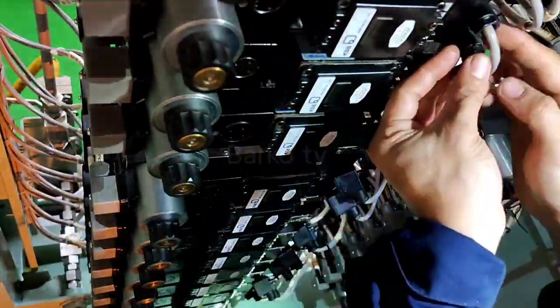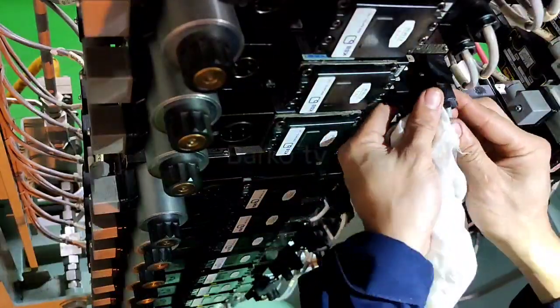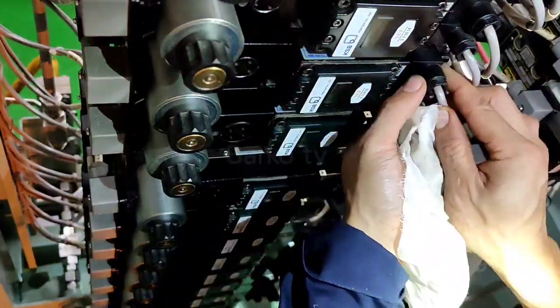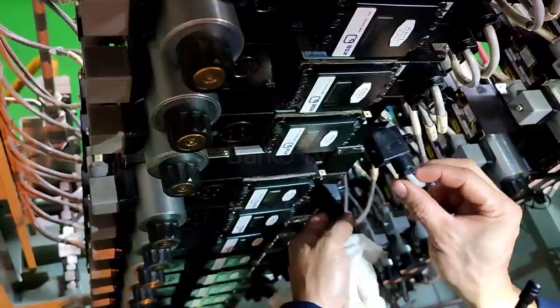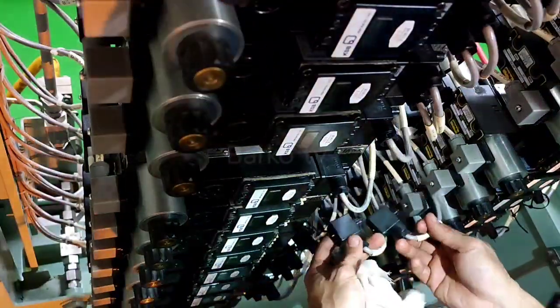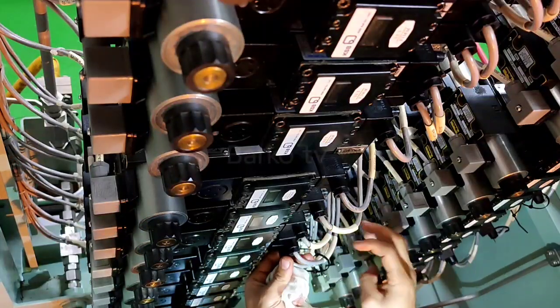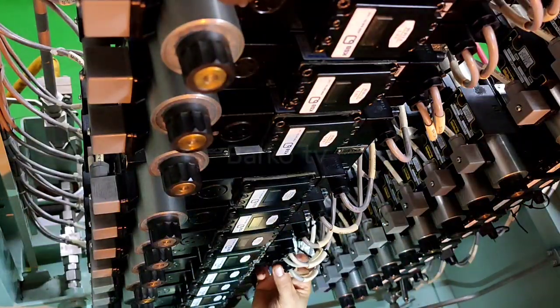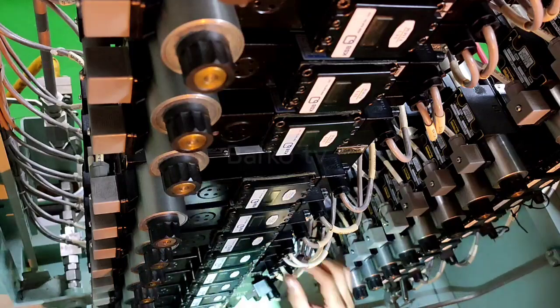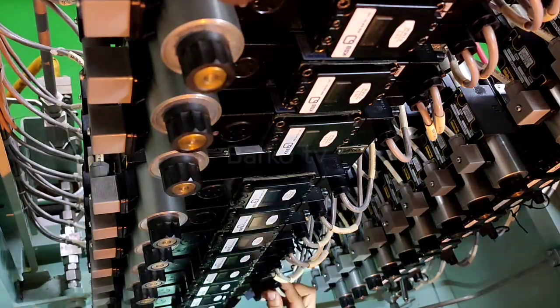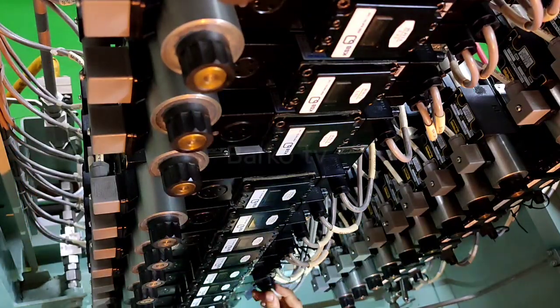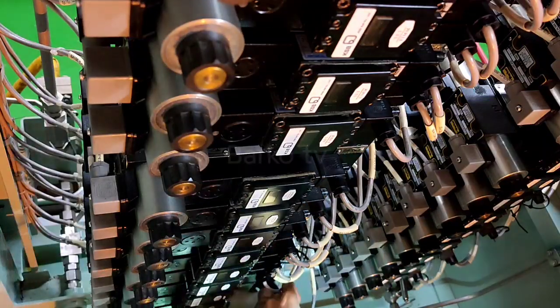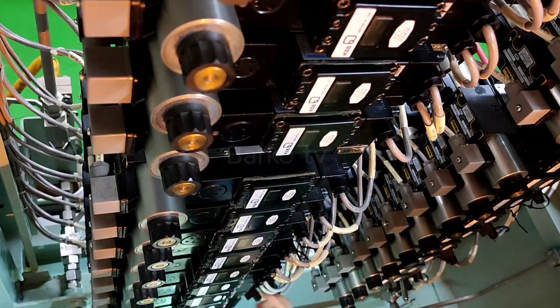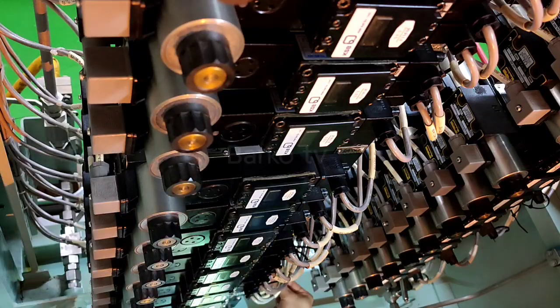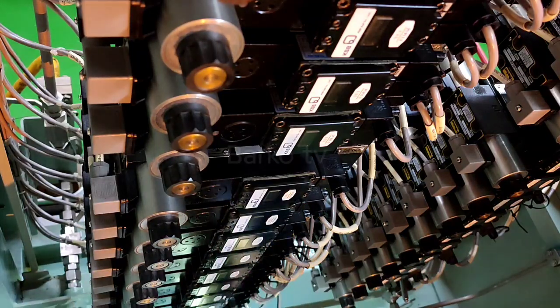By the way, we need to clean these connectors, all connectors, because that is a cause of low insulation or ground fault. We already cleaned all components, including solenoid valves, FIM indicator, flow indicator. When oil penetrates the PCB of the flow indicator, that causes a ground fault. Okay, I hope you learned from this one, and thank you for watching.